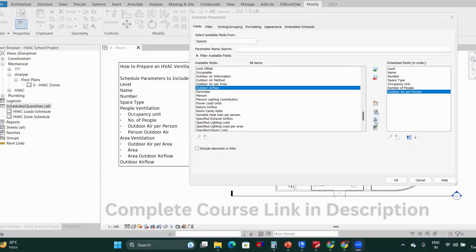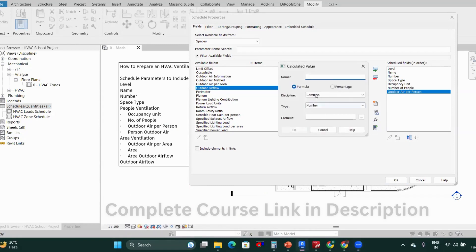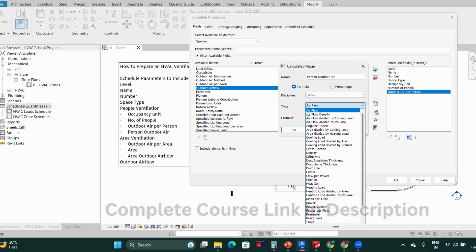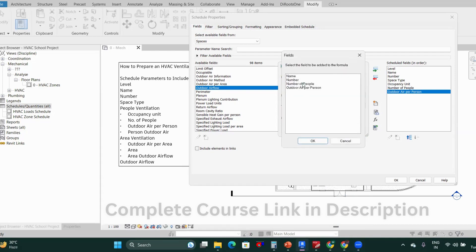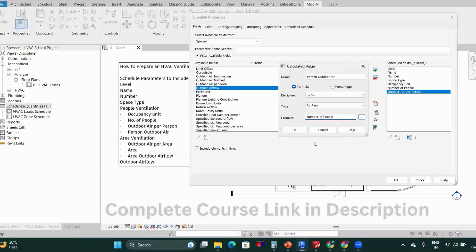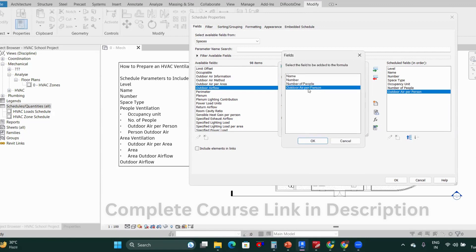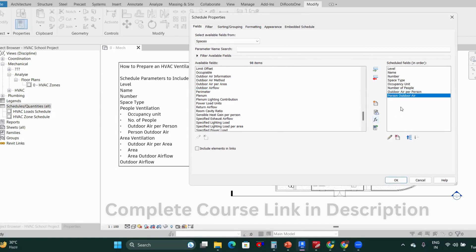Click on the calculated parameter. Name it 'Person Outdoor Air.' It's an HVAC parameter and the type is air flow. The formula is: number of people multiplied by outdoor air per person. That will give you the person outdoor air.